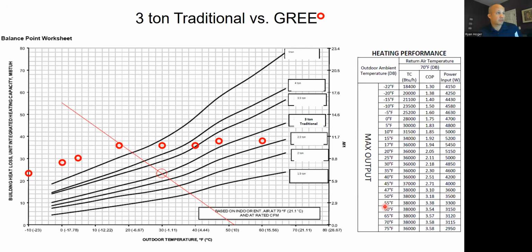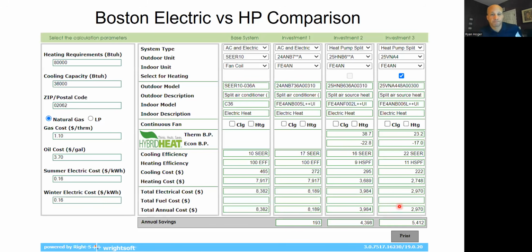If I'm looking at those software tools we were looking at before from an energy standpoint, if you remember this, I put the load information of my building in. I picked some old existing AC they had, and then I had different upgrade options here. And it told us our various paybacks. I'm going to ignore that for right now, which is all good info, but right now I want to look at these two numbers, thermal balance point and economic balance point. And once again, this software tool, the specific one, is for small systems like residential type systems. For bigger systems, usually I'll use HAP or something like that to energy model.